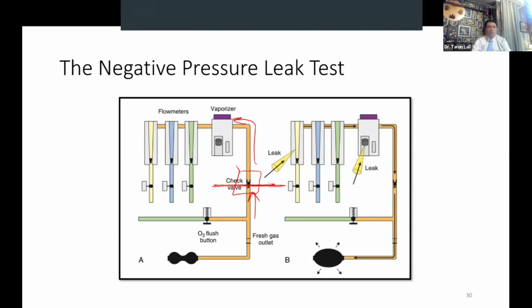So the only method left to me to check the system is that I create a negative pressure here and I see if this balloon remains collapsed for 10 seconds. Then I assume that there is no leak. If that balloon reinflates, then I can suspect that there is a leak somewhere upstream, because that is from where the air has entered and it has led to the balloon re-expanding. So this is the funda behind the negative pressure leak test.